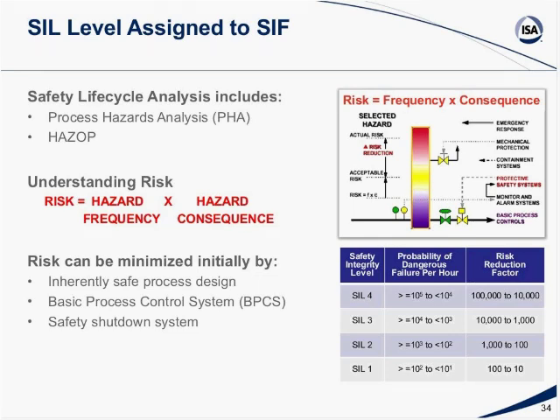So if you look at this diagram on the right, you will see that there is a particular risk that is there in your process. There is an acceptable risk as well, and there is an actual risk after doing a hazard analysis. So the difference between your actual risk and your acceptable risk is the amount of risk that needs to be reduced for your particular process. So now, suppose you find out that your risk reduction factor is between 10 and 100. If you look at the bottom right figure, you see that if your risk reduction factor is between 10 and 100, then for that particular SIF, you remember that a SIF is your safety system, your valve, and your final control element, your SIL level would be 1. But then if you find out that you actually need to reduce a lot more risk and your risk reduction factor is between 100 and 1000, then your safety integrity level would be SIL 2, and so on.